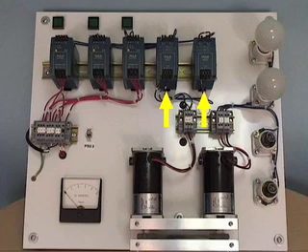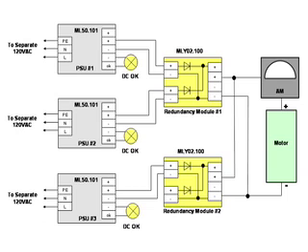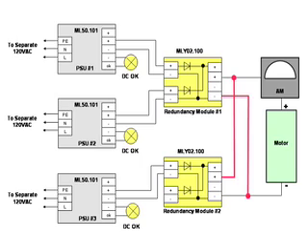These two modules over here are dual input decoupling diodes, or redundancy modules. The panel is wired per the following schematic. The output of power supply number one goes to the first input of the redundancy module. The output of power supply number two goes to the second input of the redundancy module. The output of power supply number three goes to the first input of the second redundancy module, and since we do not have a fourth power supply, the second input of that redundancy module is left unused. The outputs of the modules are tied together to make one common bus, and then pass through the ammeter on the way to the motor.